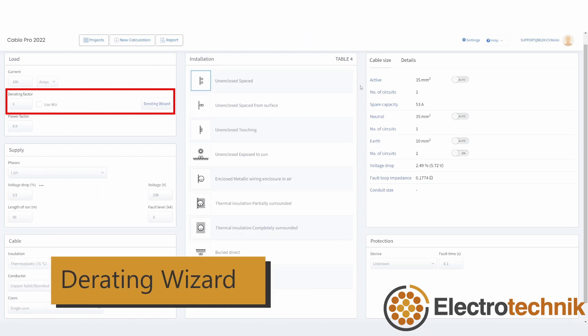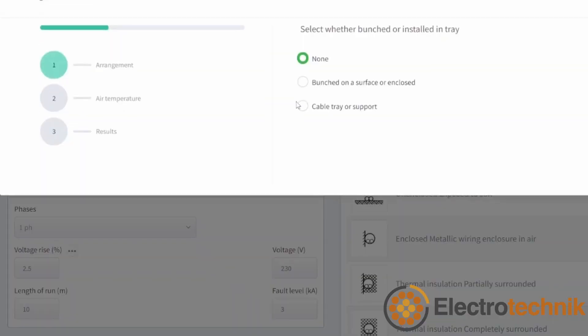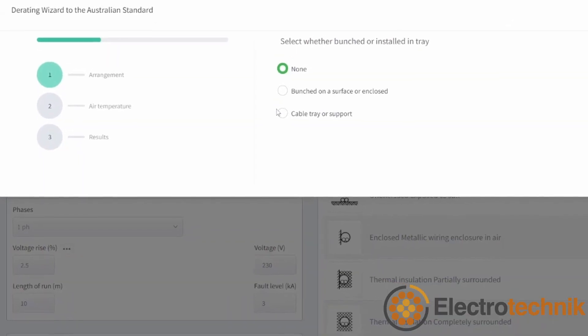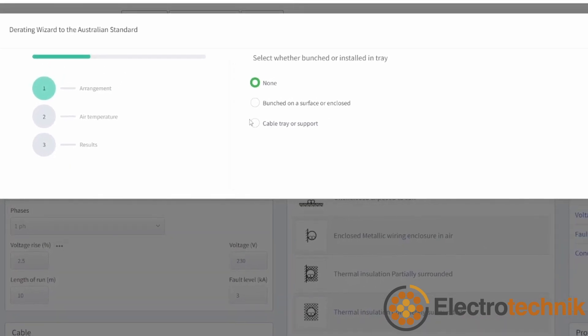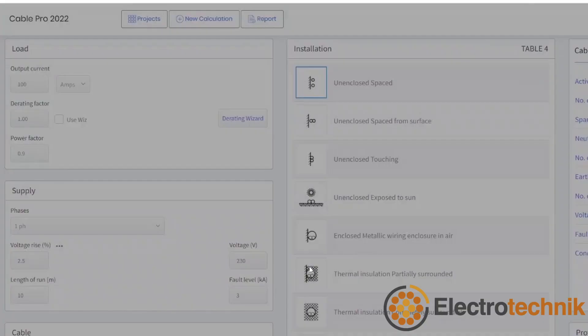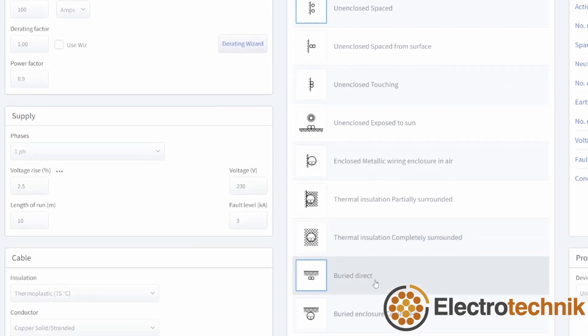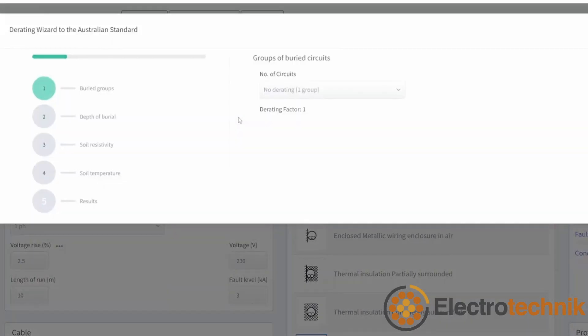Now let's have a look at the derating wizard. Once the installation method has been selected, it's a good time then to use the derating wizard to calculate the derating factor. There are two different sequences of steps for the derating wizard depending on whether the cables are installed in air or buried. Notice if I switch to another installation method, then the derating wizard changes. I will use the buried installation as an example.